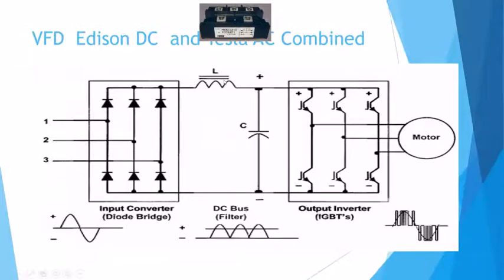You get losses in your inductors, there'll be line reactors, you get losses in your diodes, you get losses in here. So this on average can be about 3% of the total power. Then you put this, could be another 2 or 3% here, and then they put another line reactor on the output, and then you've got another 2 to 3%. So all of a sudden you may have 5 or 6% loss.